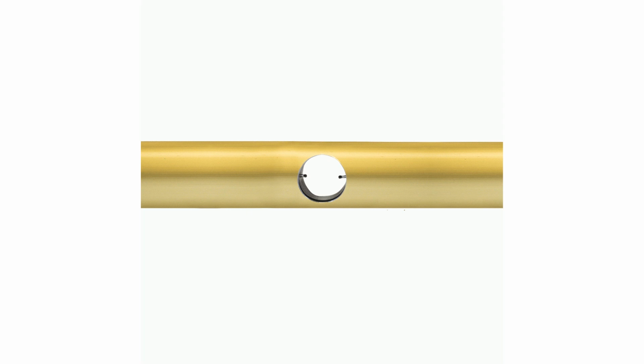Coming to the fan discharge and fan inlet, it's still the same. Only that you don't have to select the probe depending on the diameter or the circumference of your fan inlet or the fan discharge. There are accessories which you will get to record the airflow coming or pushed from the fan and goes back to the board, where you again get the measurement of your airflow as a voltage or current signal or probably a communication protocol. The same thing goes while you're measuring the water flow as well.